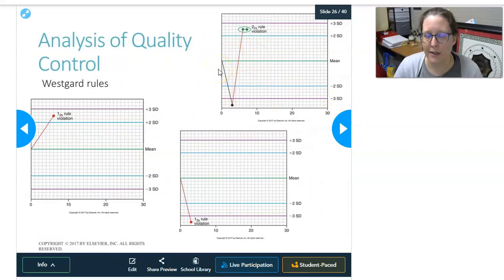Okay, so to analyze these Levey-Jennings charts, there is a set of rules called the Westgard rules that we can use to denote what's going on with our quality control. So, for example, if you have 1 point that fell outside of 2 standard deviations, you can denote that as a 1 2s. So 1 point outside of 2 standard deviations. If you have 2 points outside of 2 standard deviations, 2 in a row, it has to be 2 in a row. It can't be that it was out and then a few days later it was out again. No, it's back to back. They're 2 in a row. Then that would be a 2 2s. Okay, 2 points outside of 2 standard deviations. This can be above or below.